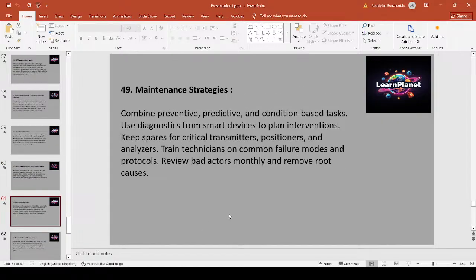Maintenance strategies combine preventive, predictive, and condition-based tasks. Use diagnostics from smart devices to plan interventions. Keep spares for critical transmitters, positioners, and analyzers. Train technicians on common failure modes and protocols. Review bad actors monthly and remove root causes.